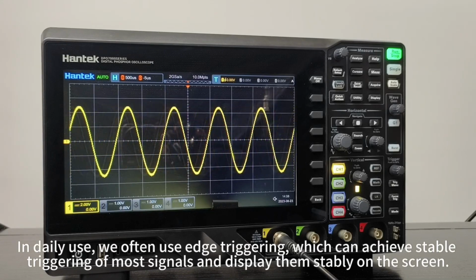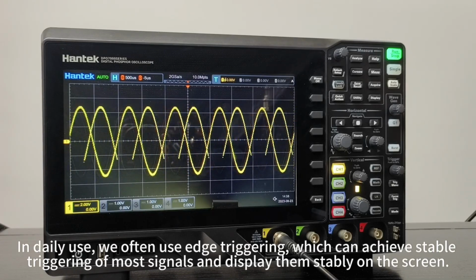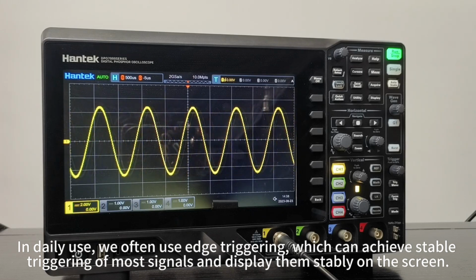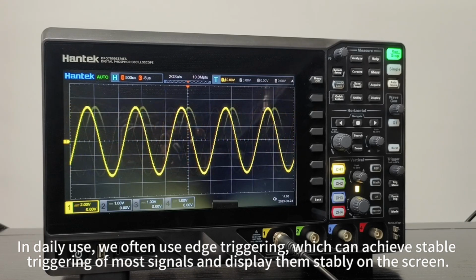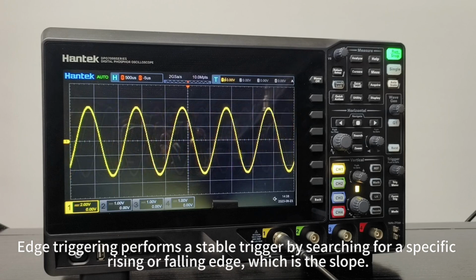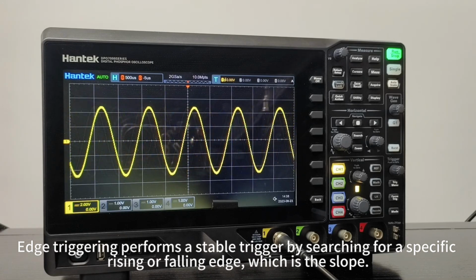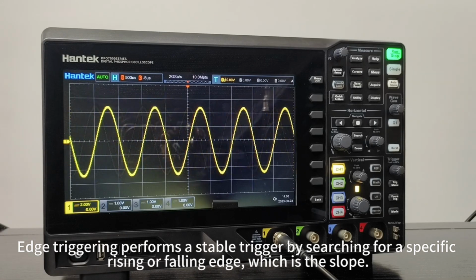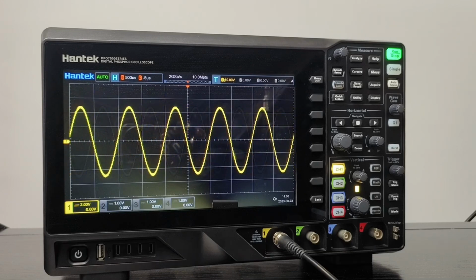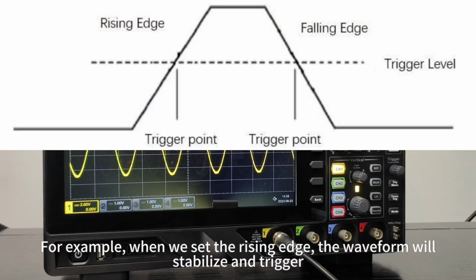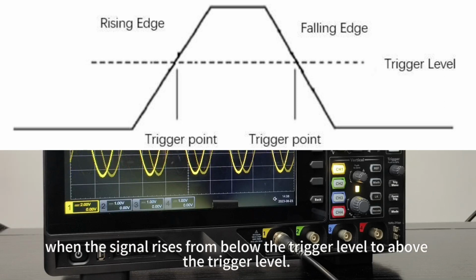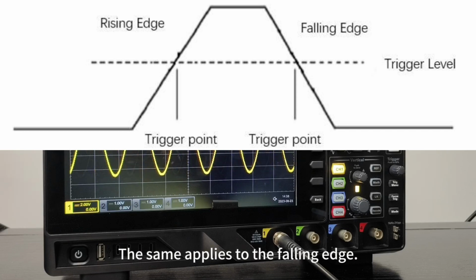In daily use, we often use edge triggering, which can achieve stable triggering of most signals and display them stably on the screen. Edge triggering performs a stable trigger by searching for a specific rising or falling edge, which is the slope. For example, when we set the rising edge, the waveform will stabilize and trigger when the signal rises from below the trigger level to above the trigger level. The same applies to the falling edge.